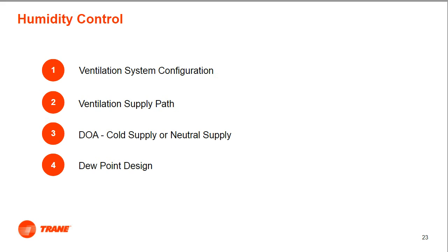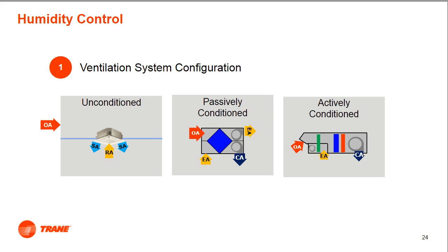When it comes to outside air delivery into a space, there are 3 main methods: delivering unconditioned air, sometimes via a booster fan, to a zone terminal unit. There's delivering passively conditioned air with the use of an energy recovery ventilator, and delivering actively conditioned air via a DOAS or makeup air unit. Depending on your outside air requirements and the total system design, one of these three methods will suit your ventilation requirements.